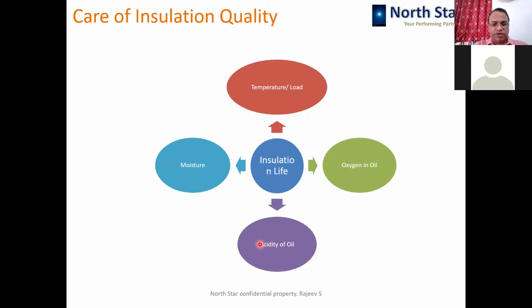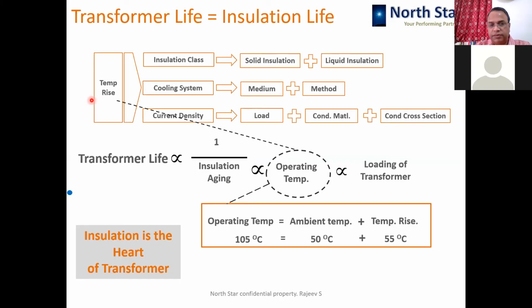Acidity, the rate of increase of acids in the transformer oil, and oxygen in the oil. So these four factors primarily define or limit the life of the transformer, or they affect the insulation quality of the transformer.